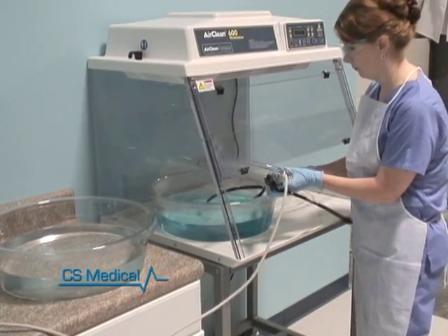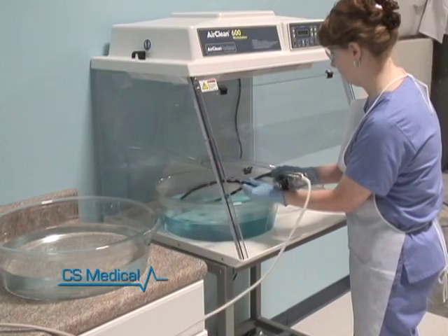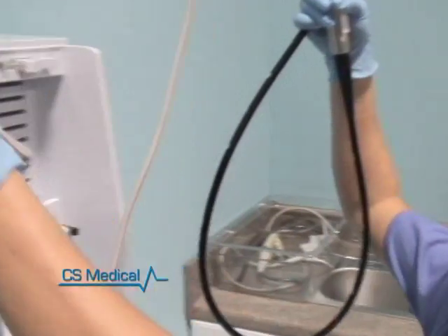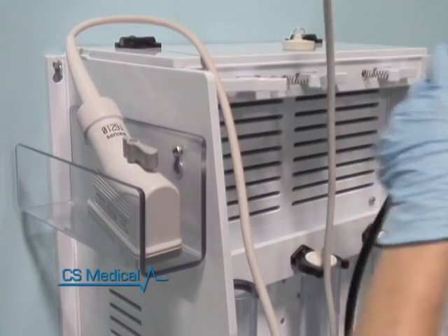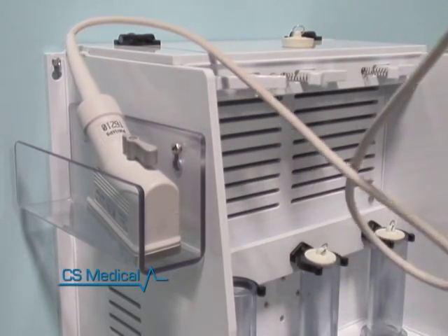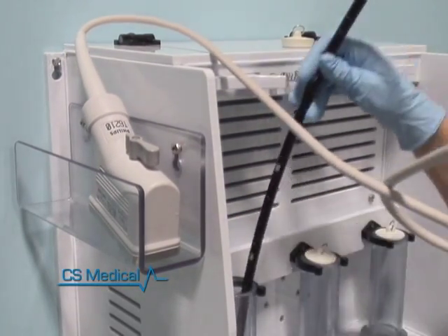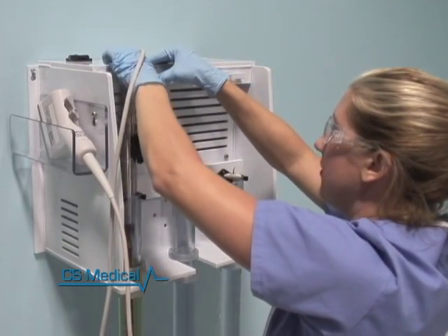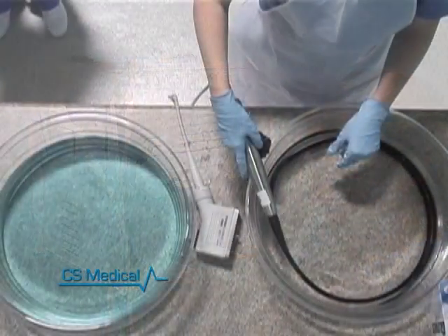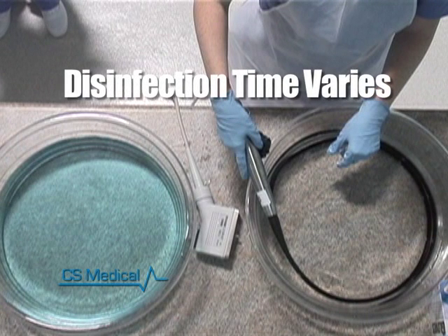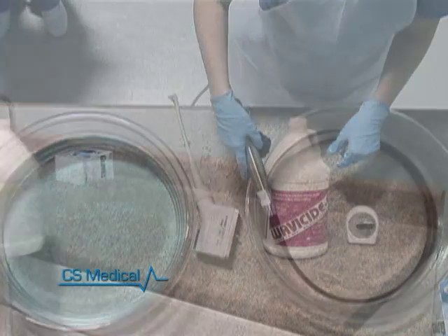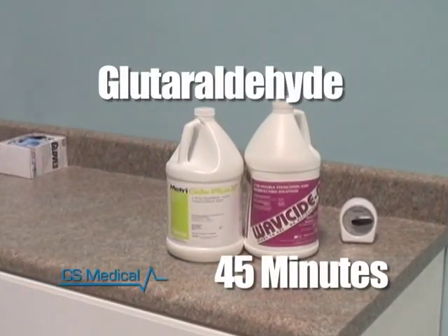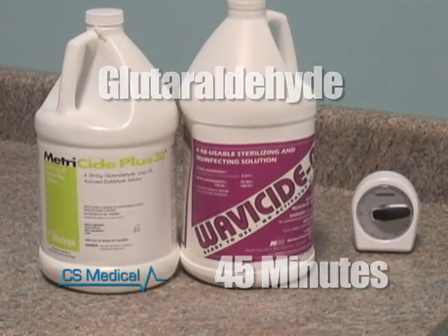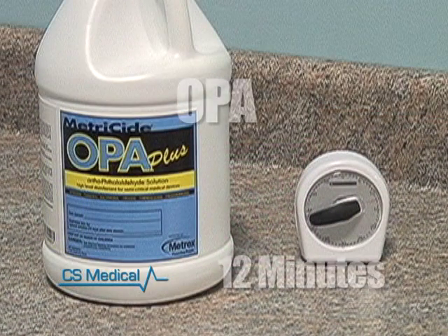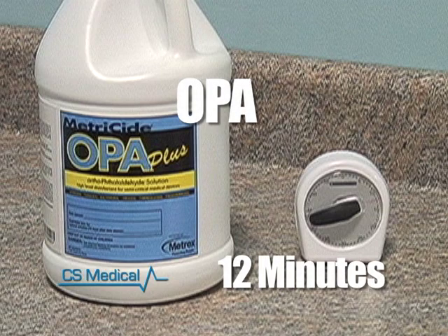Then the TEE probe is placed into a large bowl of disinfectant or into a tube that is part of a wall-mounted device for disinfection and vapor management. This system uses less disinfectant while providing a level of exposure control from the disinfectant. The actual disinfection time depends on which disinfectant you use. Glutaraldehyde-based disinfectants such as Cidex, Wavicide, or Metricide require 45 minutes for complete disinfection. OPA, on the other hand, only requires 12 minutes.